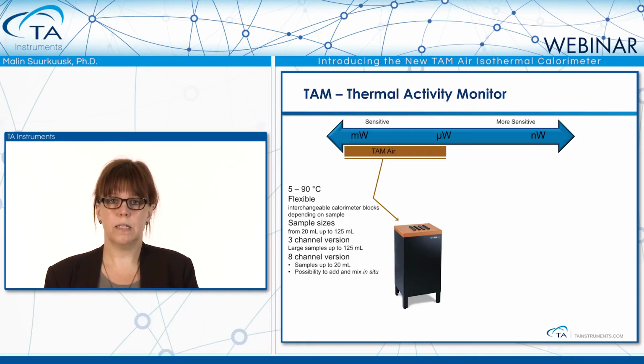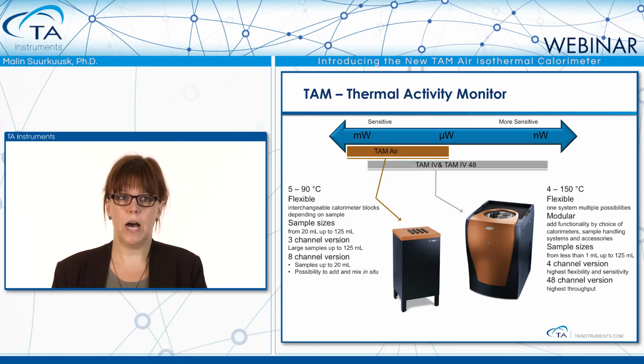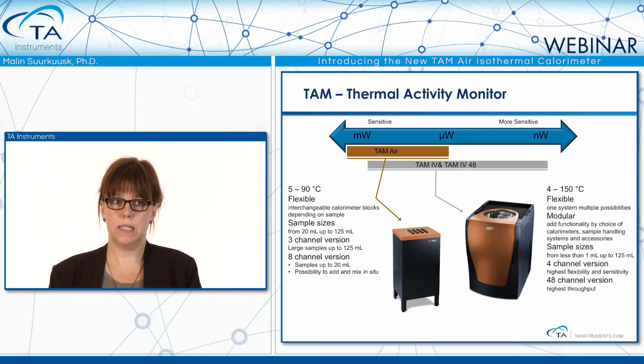But for some applications, the sensitivity of the TAM Air is not enough. Then we also have the TAM 4. It's the more flexible calorimeter. It has much more sensitivity. It goes over the whole sensitivity range, back to nanowatt sensitivity. And this is a completely modular system that you can build up to your own needs, from very small samples below 1 milliliter up to 125 milliliter samples in this case. So depending on the needs, there is the TAM Air, which is perfect for cement and concrete and food applications. If more sensitivity is needed, there is also the TAM 4.